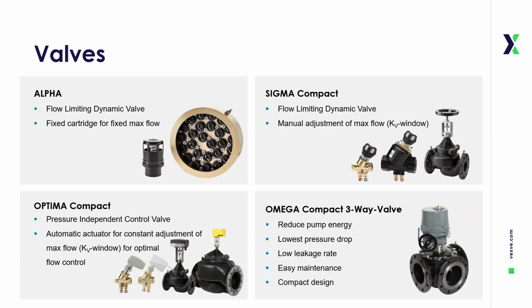The Sigma Compact Flow Limiting Dynamic Valve goes a step further, offering manual adjustment of the flow by a handle that will adjust the opening of the valve, thus allowing flexibility to fine-tune the system after the installation process. The Optima Compact Pressure Independent Control Valve is equipped with an automatic actuator that constantly adjusts the flow to all flows between design load and zero. This ensures optimal control, stability, and efficiency, even under varying system conditions.